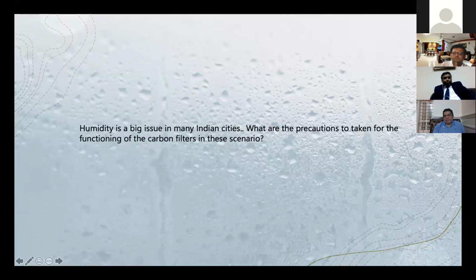Yeah. I want to make a point. When you are using a charcoal filter in any of the pre-filter stage, it's important to use a semi-HEPA after the charcoal filter. Because charcoal, in whatever methodology you pack it as a filter, will emit micron-sized charcoal particles. So please make sure that there is a semi-HEPA immediately after the charcoal filter.